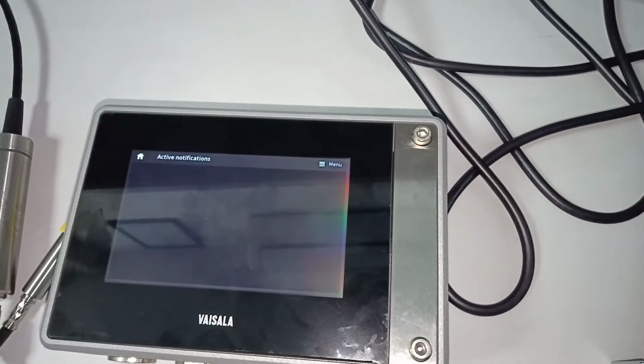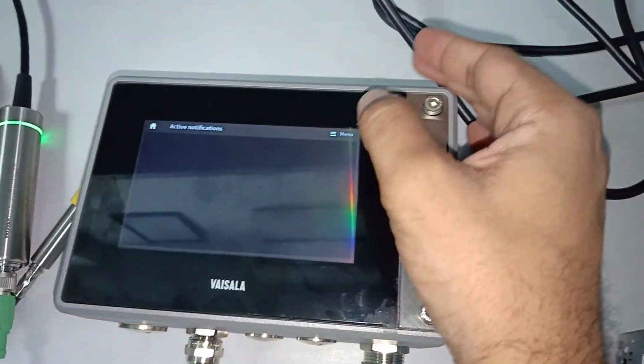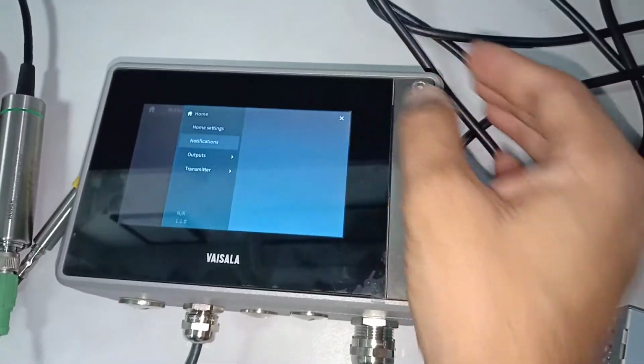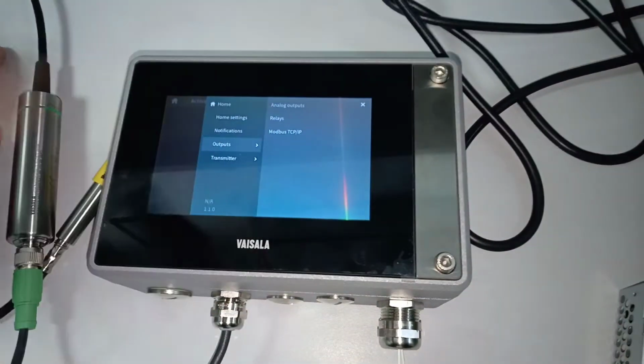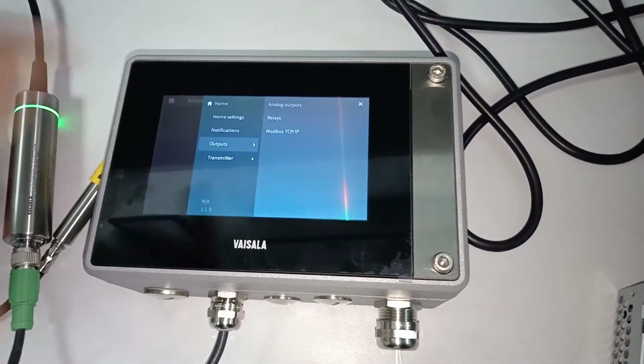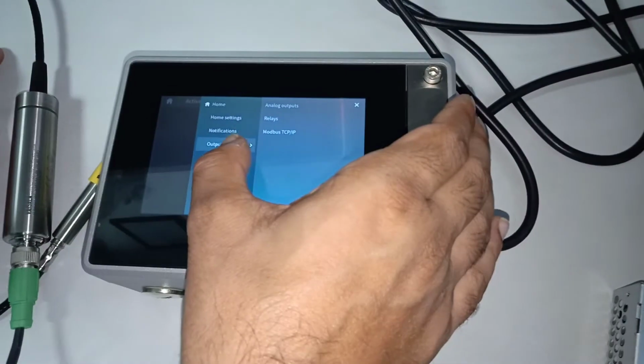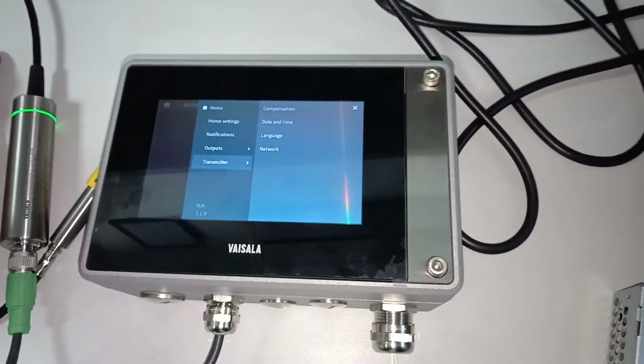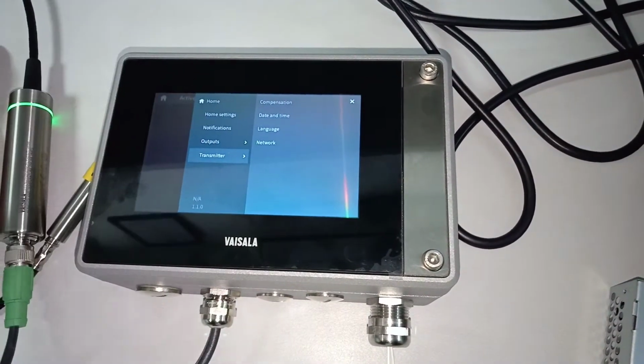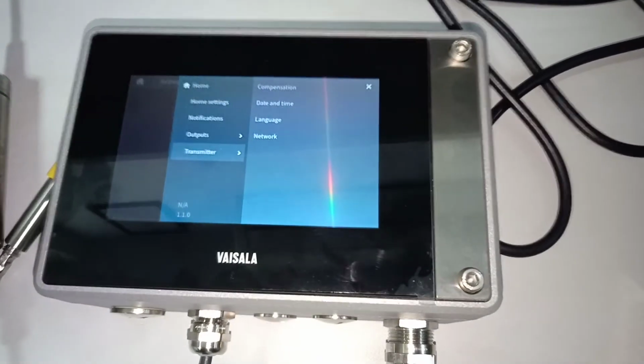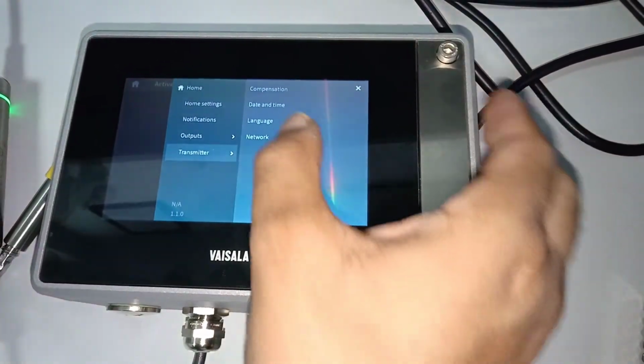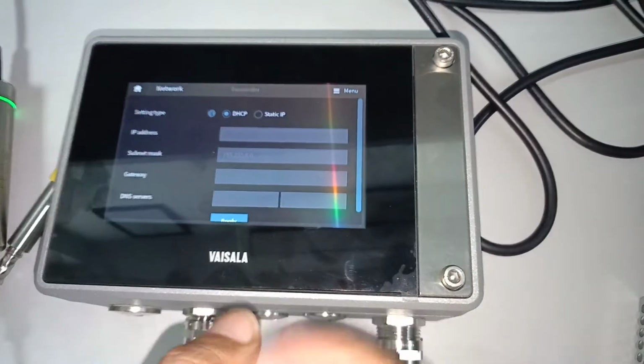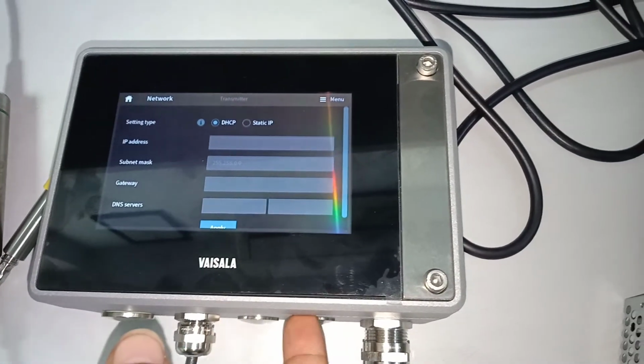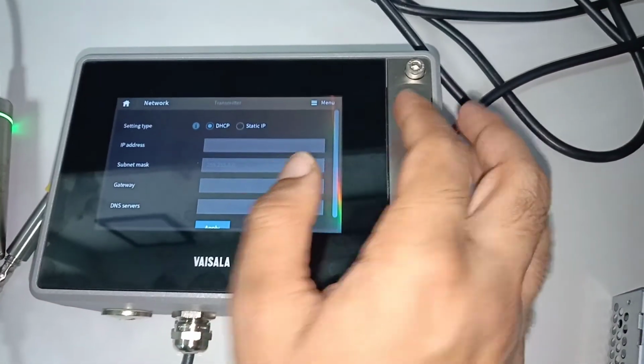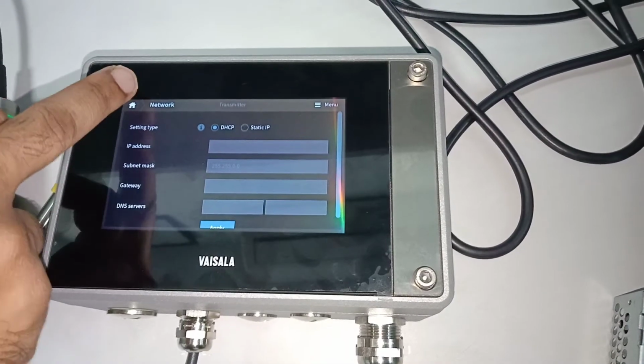In notifications, you will receive the notifications for any alarm or something, maybe any malfunction. In outputs, you get the outputs: analog output, relays, Modbus TCP/IP. In transmitter, you can set the date and time. Compensation can be set, language, and then you have network. In network, you just connect. When you connect the Ethernet cable, you put the static IP and you can see the readings on your local network.